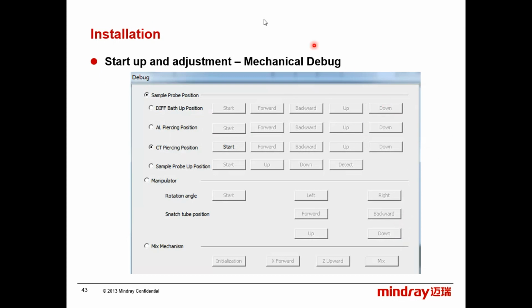So for the mechanical adjustment, of course you need to check and confirm, or adjust if necessary, the sample probe position. So what do we have for the sample probe? You have the diff bath, the AL piercing position, the autoloader piercing position, this one on the rack, to make sure that the probe is well centered when it pierces the tube. And this is for the closed tube piercing position. This is the manual loading position.